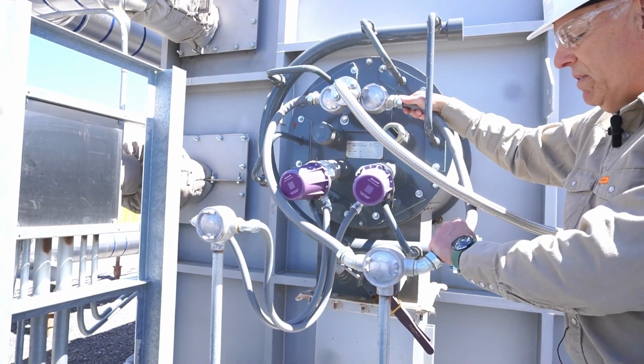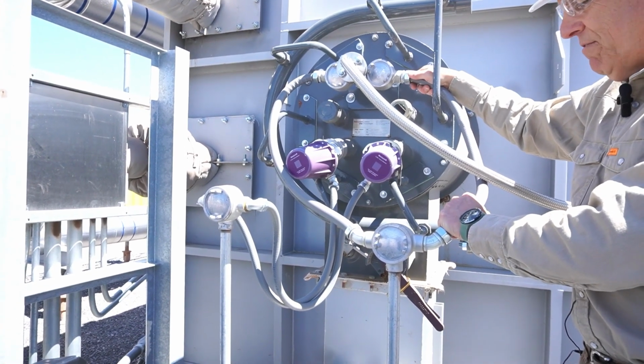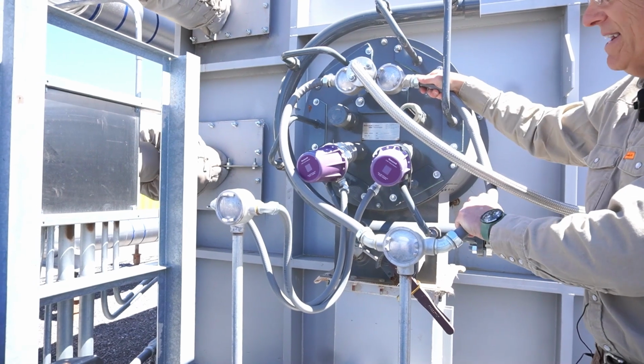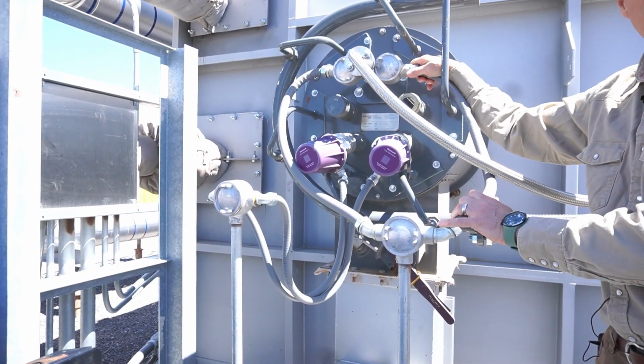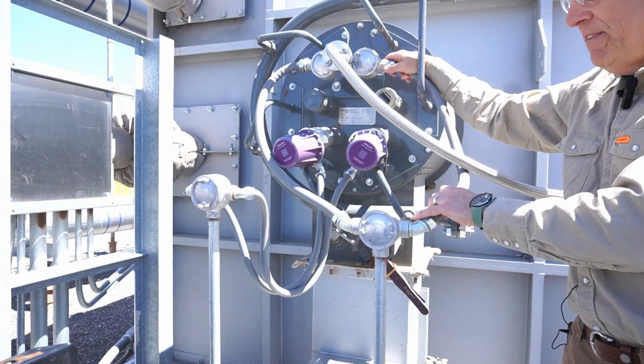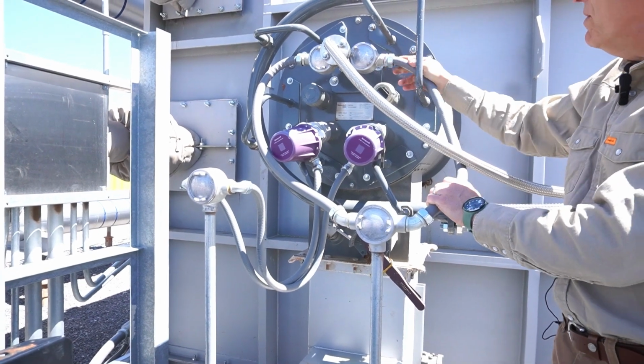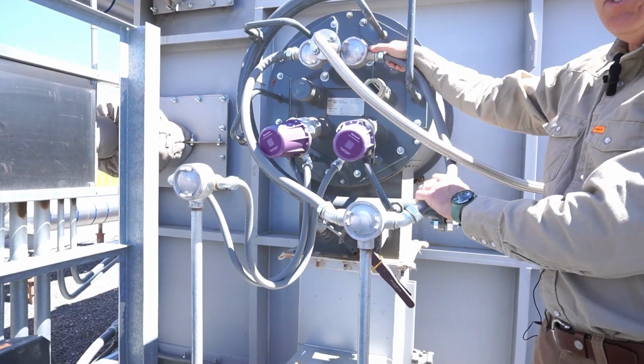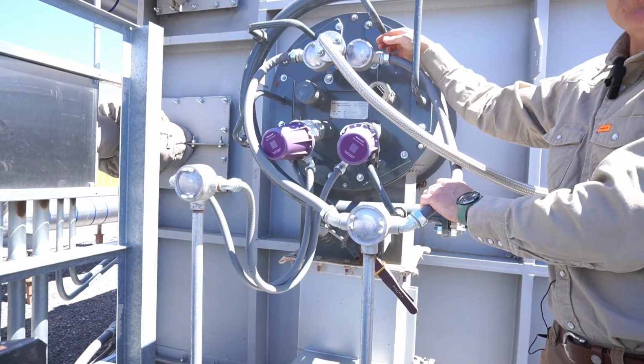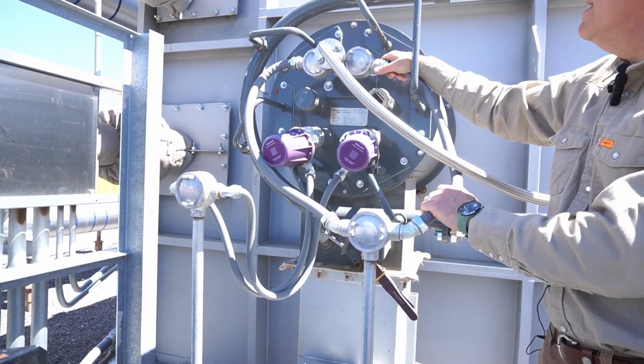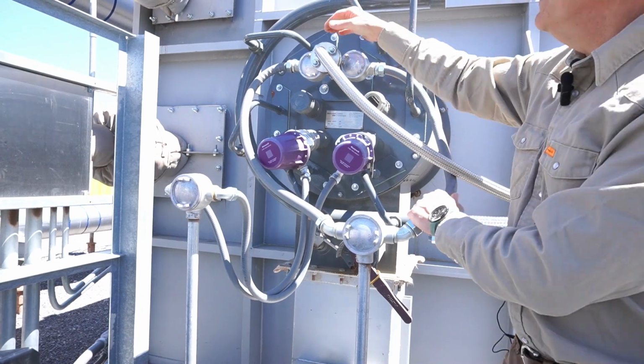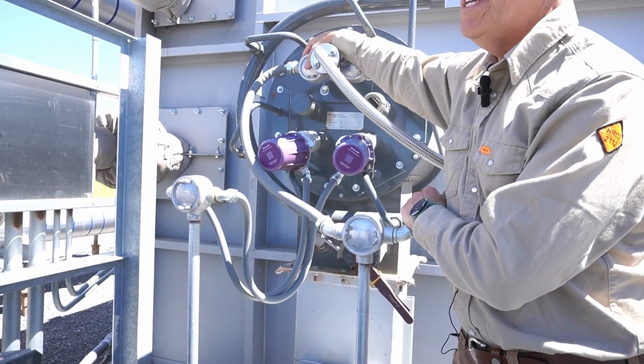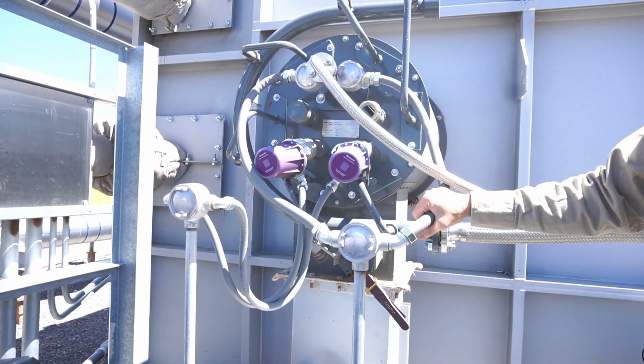There's a high voltage signal sent to the pilot via transformer, ignition transformer. That high voltage goes to the tip of the pilot, and there's a spark created and it ignites the pilot. And then on the other side would be the flame rod sensing that I do have a lit pilot.